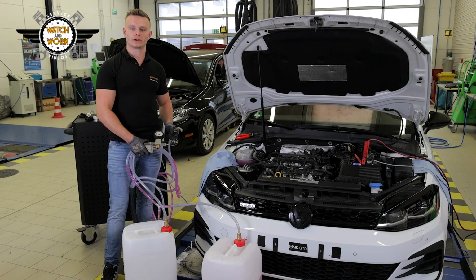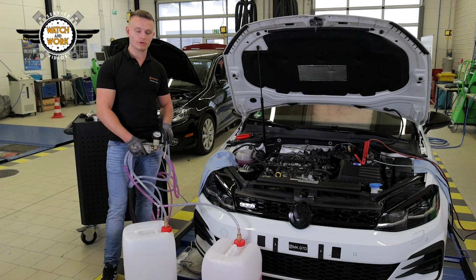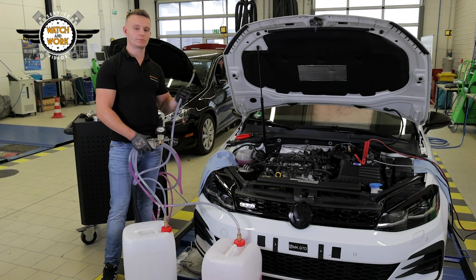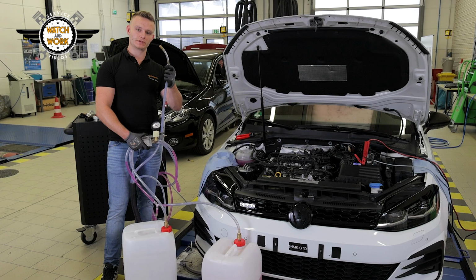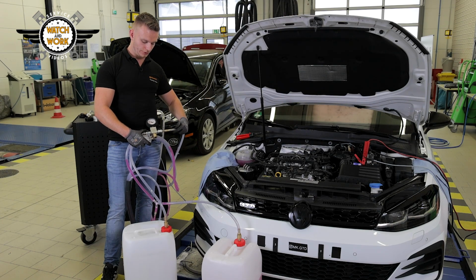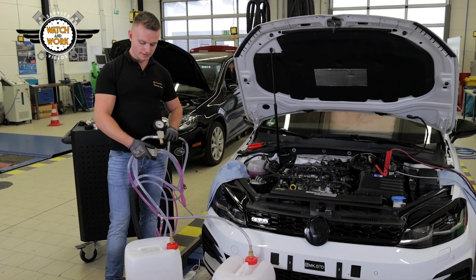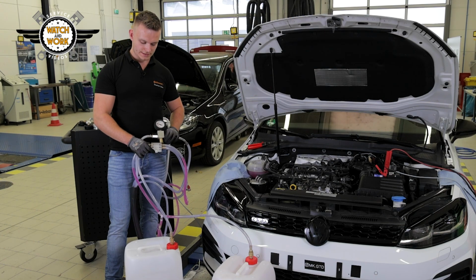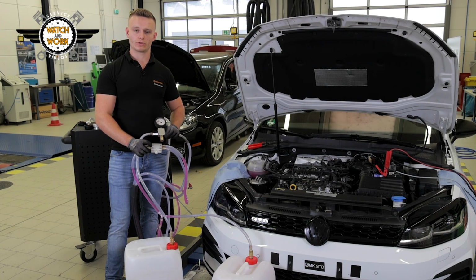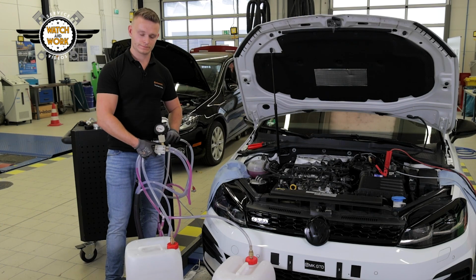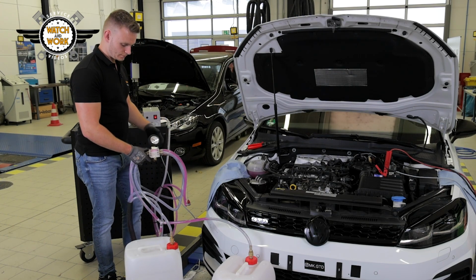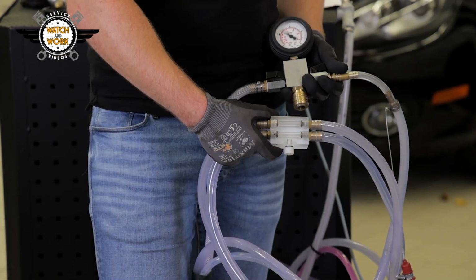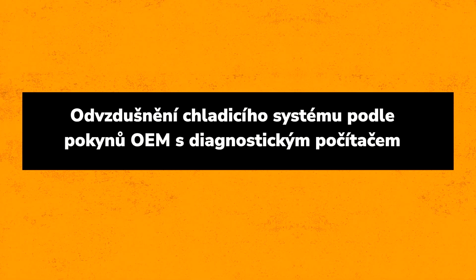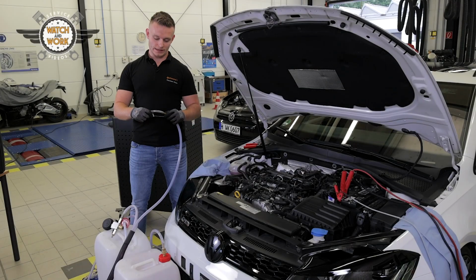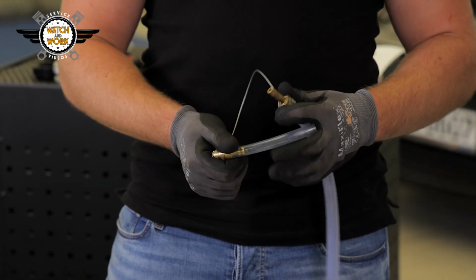Finally, the equipment needs to be cleaned. For this, put the suction hose from the container in a container of distilled water. We detach this hose from the return hose. We then connected our adapter to it. You now attach this to stopcock B so that we can clean the entire appliance. The reason for doing this is to prevent the inspection glass from becoming discolored due to the coolant. Last of all, you disconnect the flush hose again and fit the plug onto it.